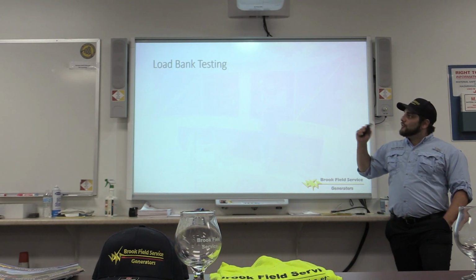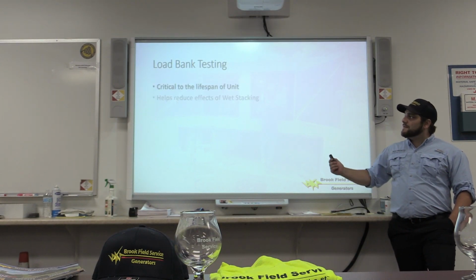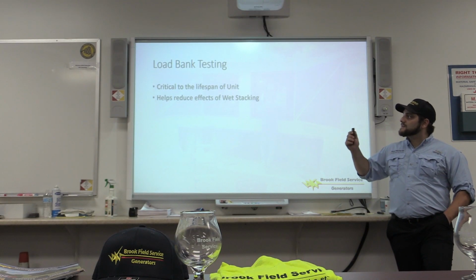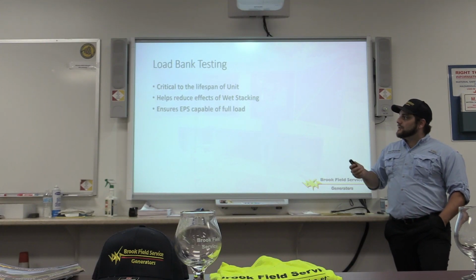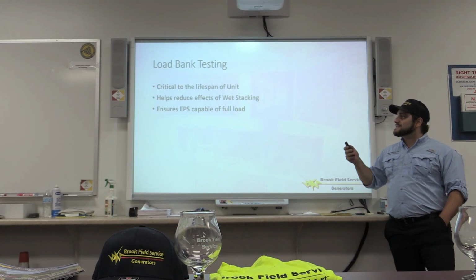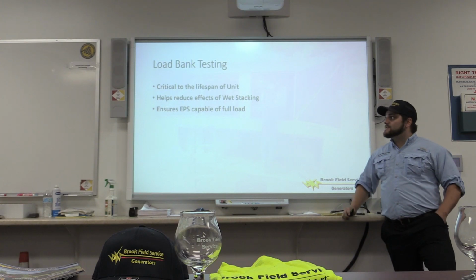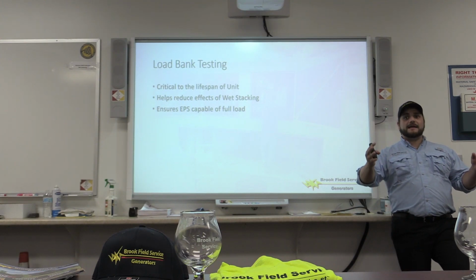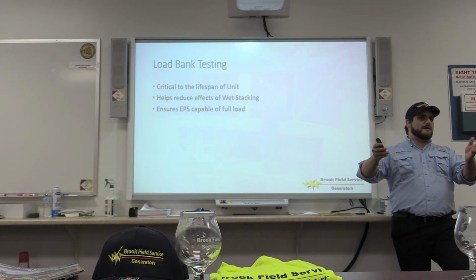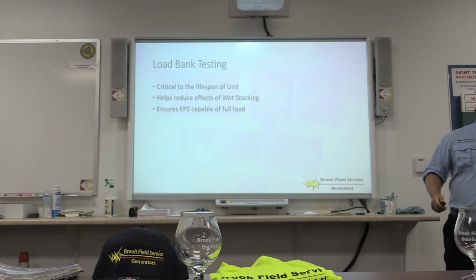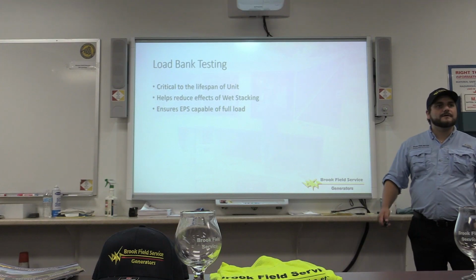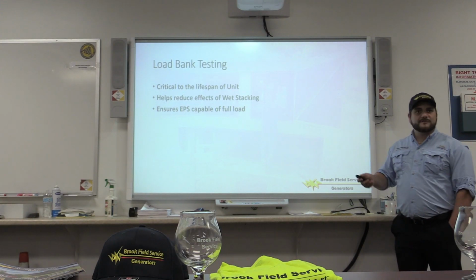A quick comparative about load bank testing. It's critical to the lifespan of the unit, helps reduce the effects of wet stacking, and ensures your emergency power system is capable of a full load. So we hook it up to make sure that it is able to run 100% load for how long? 4 hours? We step it up, so you run different tiers, but you basically run 2 hours under 100% load. There you go, so 100% load for 2 hours.